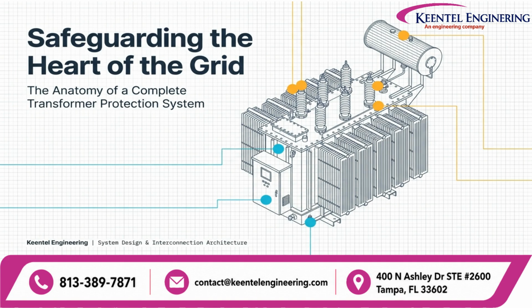Transformers are among the most critical and valuable assets in an electrical power system. They connect voltage levels, transfer enormous amounts of energy, and support the reliable operation of the entire grid. But protecting a transformer is much more than installing a protective relay. A complete transformer protection system is an engineered chain that begins with accurate measurements, continues through intelligent protection algorithms, and ultimately ends with a reliable trip circuit capable of physically isolating the fault.